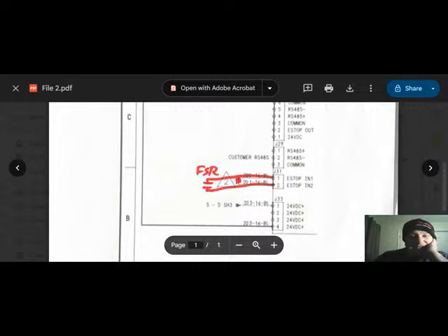Reason for that is, if you went with the normally closed contacts to maintain this loop, and you relied on the relay powering up to open the contacts and cause your restart fault, well, if that coil all of a sudden decides to burn out or something, you're not going to know it until you actually break this loop. Doing it this way, keeping the relay powered up and relying on normally open contacts to maintain the loop.